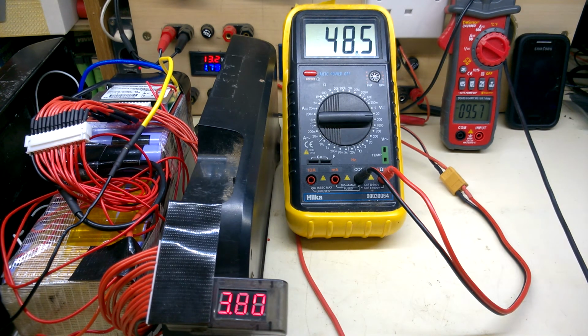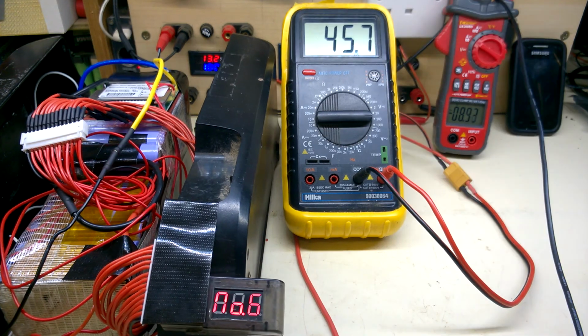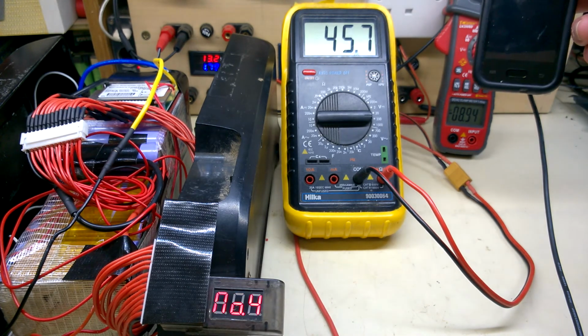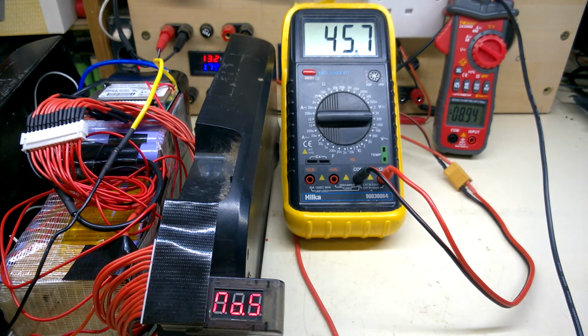Without blowing anything up. Happy with that, should have been running for about half an hour. Say, 17:01 - 29 minutes. Current's dropped to just under 9 amp. The voltage is 45.7. I think we can terminate the test there.